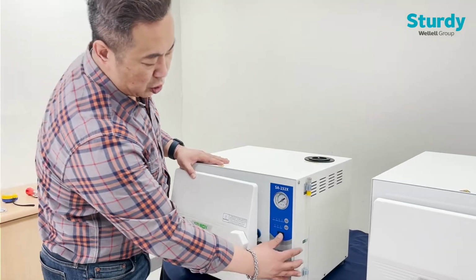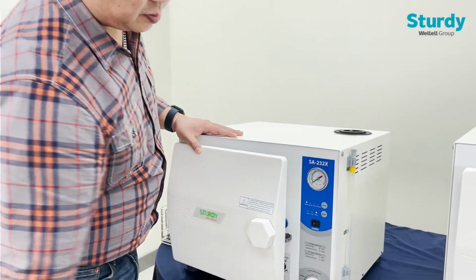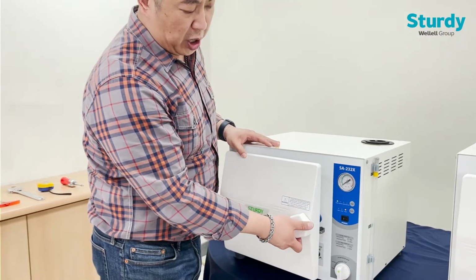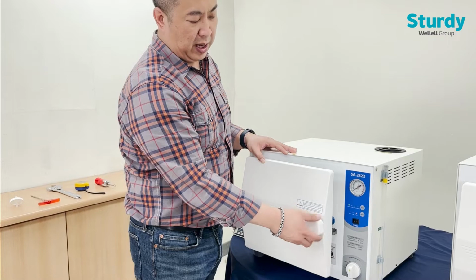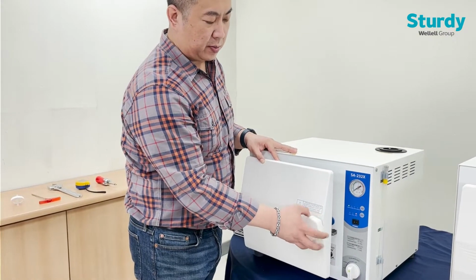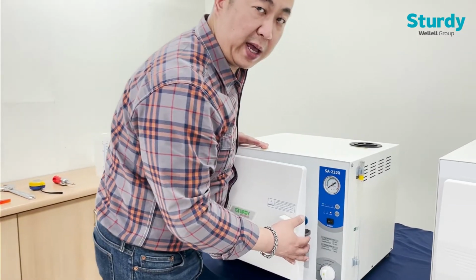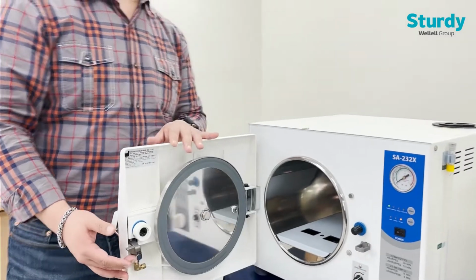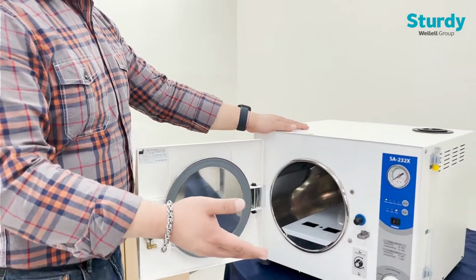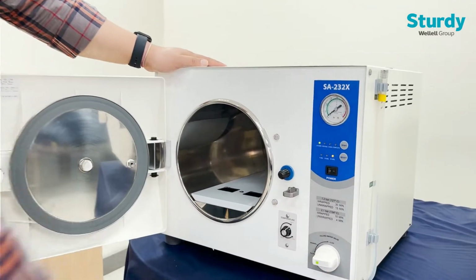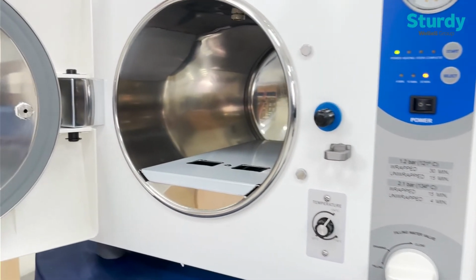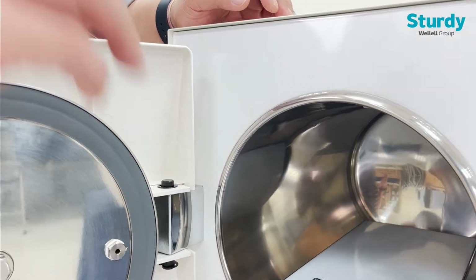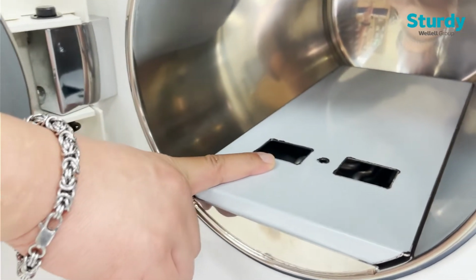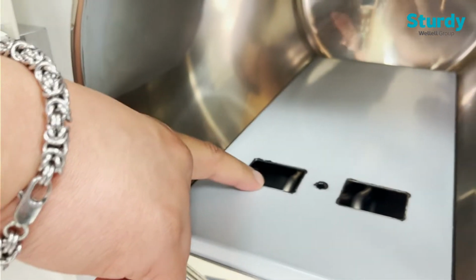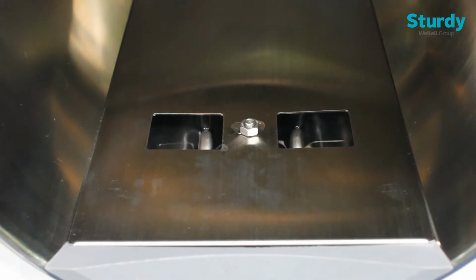Before we start the machine, we switch on the power on the control panel. Next, we will open up the chamber door by turning the handle anti-clockwise until it is fully loosened, and then lifting up the safety latch, and then the chamber door opens. Next, we will fill up the chamber with water by turning on the water valve. To verify that there is sufficient water inside the chamber, we look at the opening window on the base plate, and once the water reaches above the heating rod, that means sufficient water is available. And then we switch off the water valve.